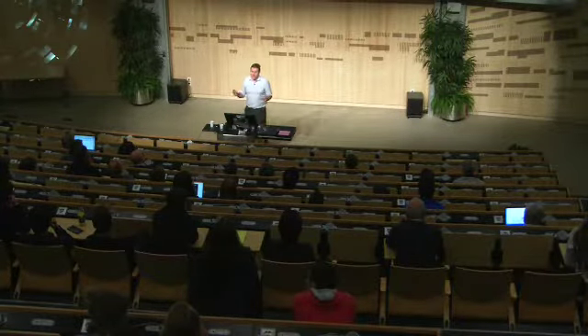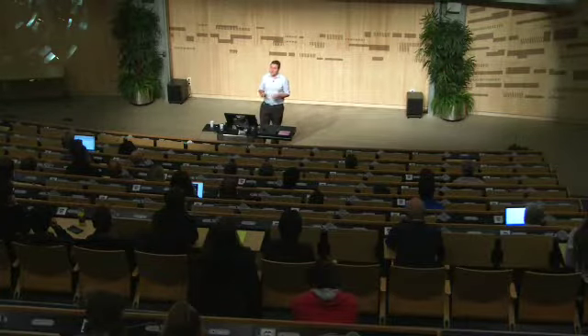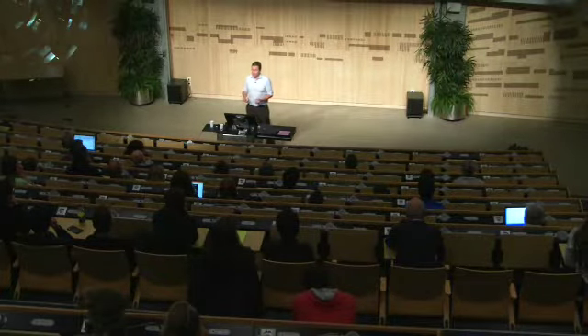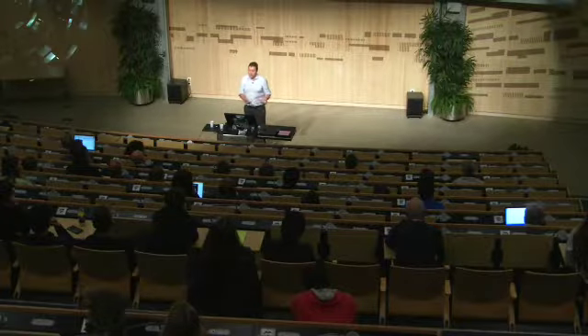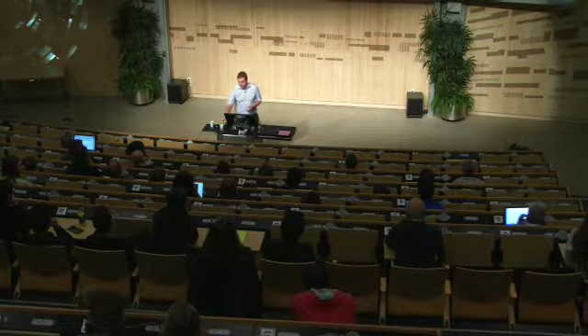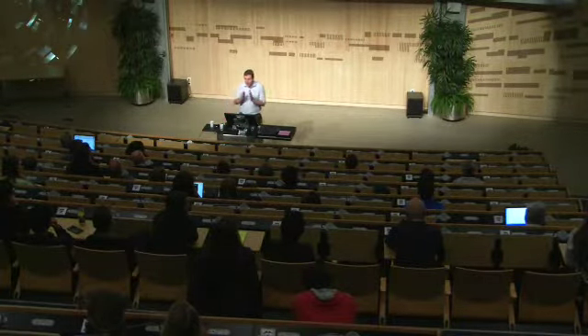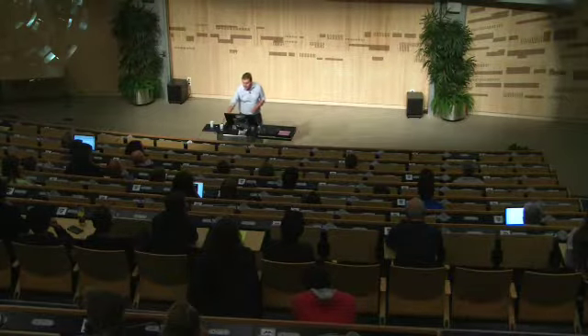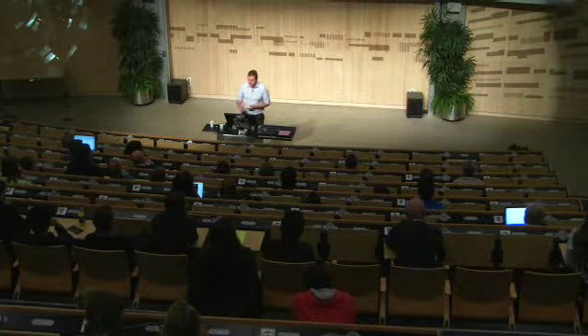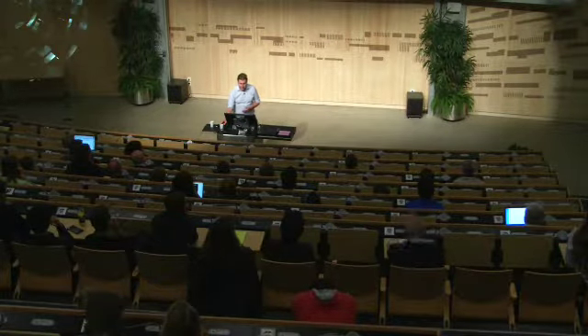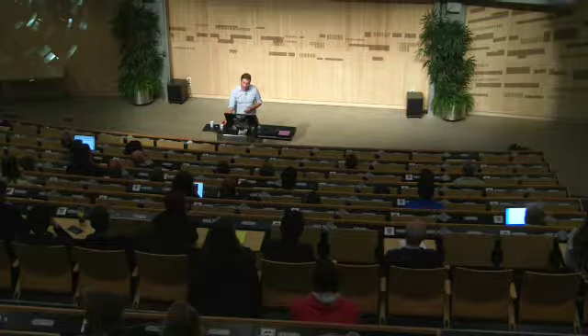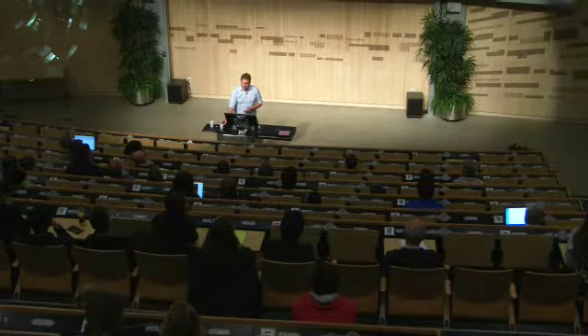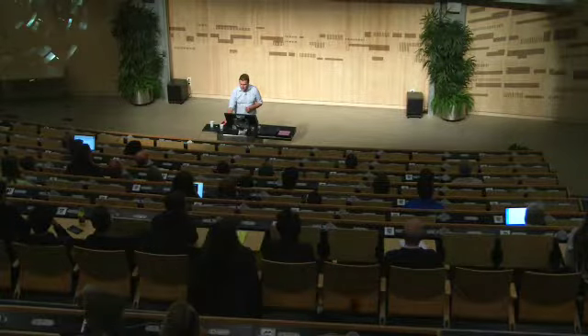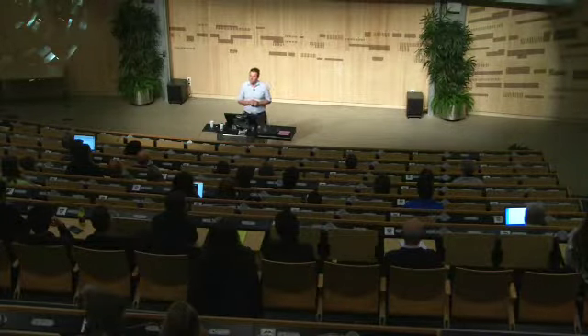That's actually an artefact because standard CTs assume all the materials are the same colour, which the whole point of this is they're not. And here we've used a Mars scan, and we've narrowed the energy range we're looking at, and the same screw, you can see you get absolutely no artefact off it. And so that's actually really important, because if I look at this image, I wonder where that black bit is, is that artefact, or is that bone not healed properly around the screw? Whereas if I look on the spectral scan, I can see that the bone metal interface is really, really good.